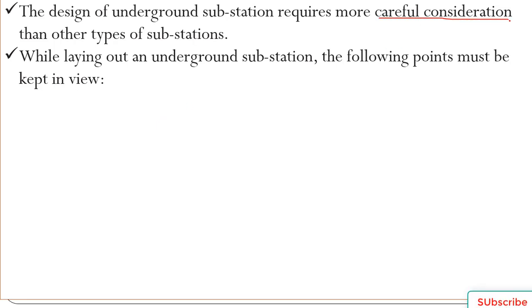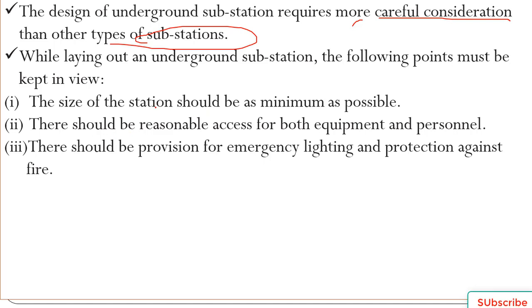The design of an underground substation requires more careful consideration than that of other substations, especially the insulation type. While laying out an underground substation, the following points must be kept in view. The first one is the size of the station should be as minimum as possible. There should be reasonable access for both equipment and personnel. There should be provision for emergency lighting and protection against fire.